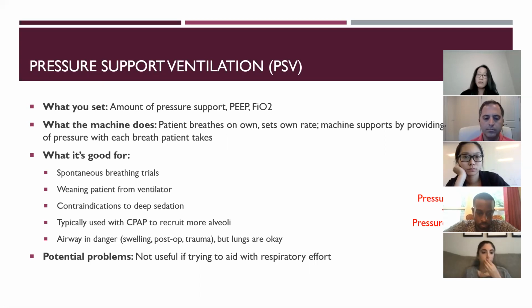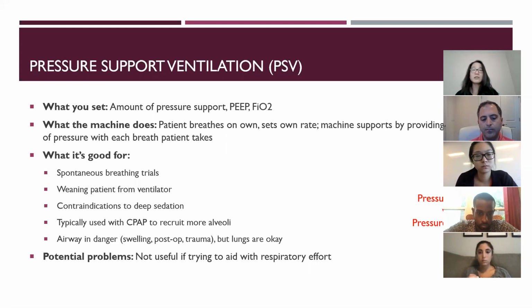So you are setting the amount of pressure support you want to give them, a PEEP, and an FiO2, and then the patient basically does the rest. What this is good for, it's good for seeing if they're strong enough to start coming off the ventilator. It's good for seeing if they're ready to breathe on their own. You can use it with CPAP and other things. It's not a new mode of ventilation. It's just a very fine mode to help the patient the best. It's not just letting them off with just CPAP or putting them under too much sedation on a ventilator. It's a nice in between. So you can use that to wean them off.